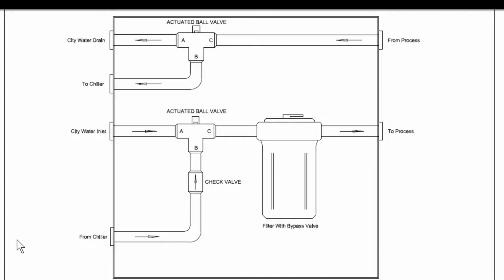Now, there's a really important thing that needs to be understood about the city water changeover panels. These are not to be applied for any process, okay? Typically the city water changeover panel is going to be applied when you have what we call a mission critical application. So an application that, regardless of what's going on with the chiller, has to be cooled, whatever it is. And that's most commonly used for, but not limited to, CTs, especially MRIs, where you could have a large catastrophic loss of helium, which is very expensive, and so these panels can really help out.